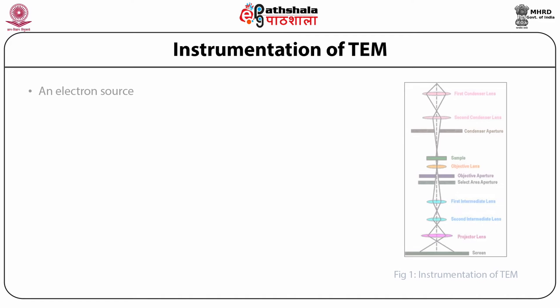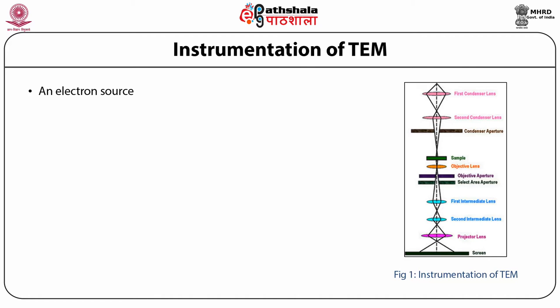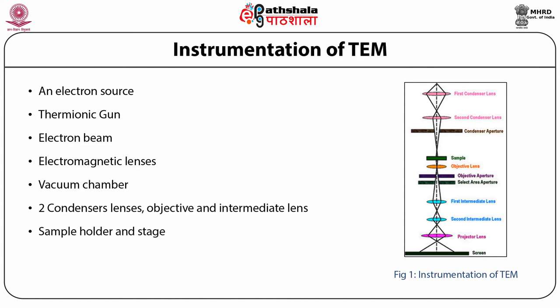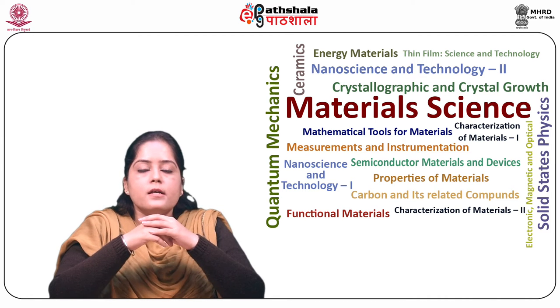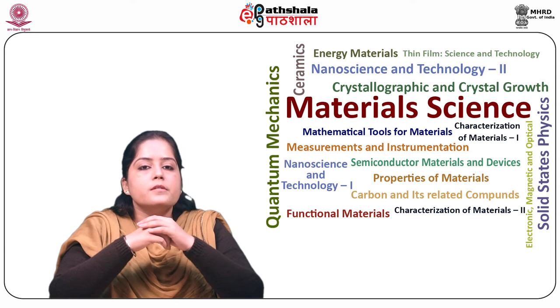This figure shows the instrumentation of TEM, where there is a source of electrons — a gun based on thermionic emission — a beam of electrons, electromagnetic lenses, a vacuum chamber, two condenser lenses, objective and intermediate lenses, a sample holder and stage. The imaging device is a phosphor or fluorescent screen interfaced with a computer.